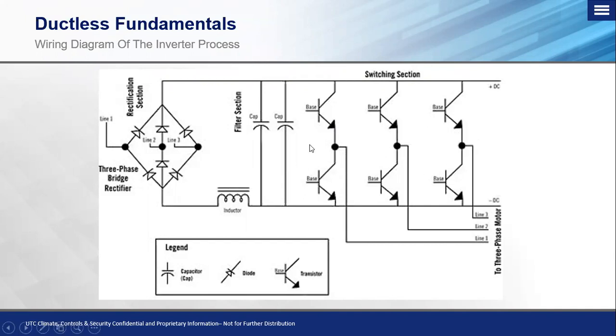Now, depending on our deviation from set point, depending on the compressor speed, depending on EXV position, it will pulse voltage to three common terminals, which we talked about as being W, V, and U. And that goes directly to our compressor, which in turn controls the speed. So when we talk about those IGBTs, this is what we're actually looking at from an electrical point of view: switches that open or close on a positive or negative DC bus that simulate an AC sine wave.